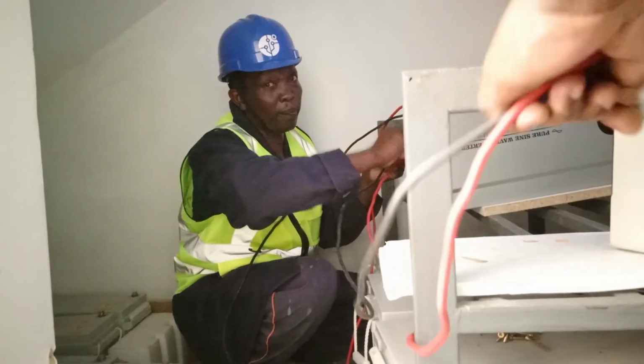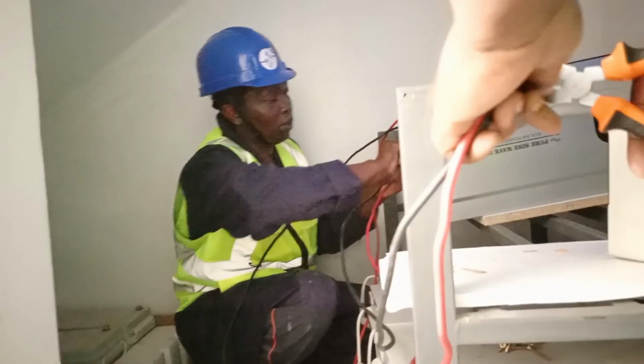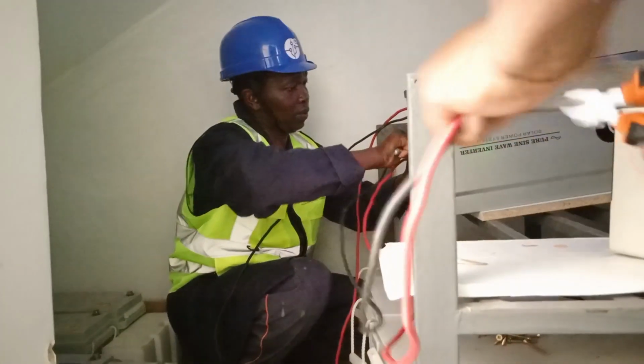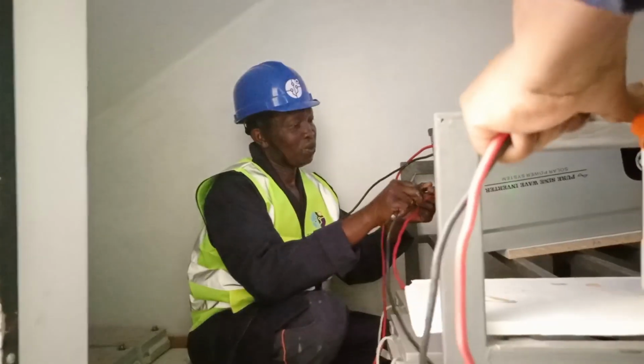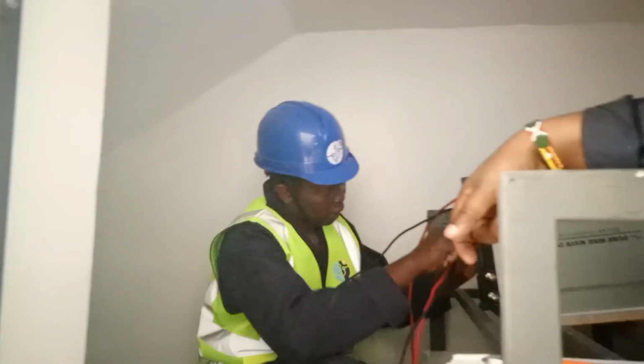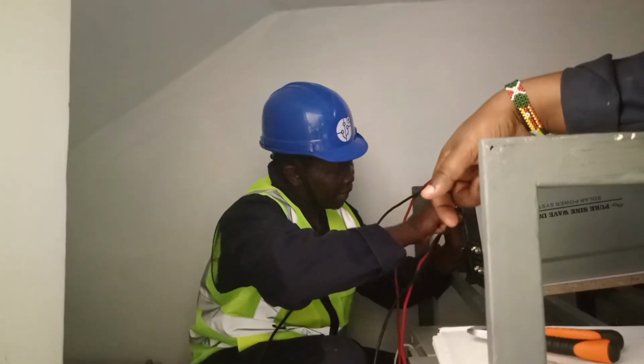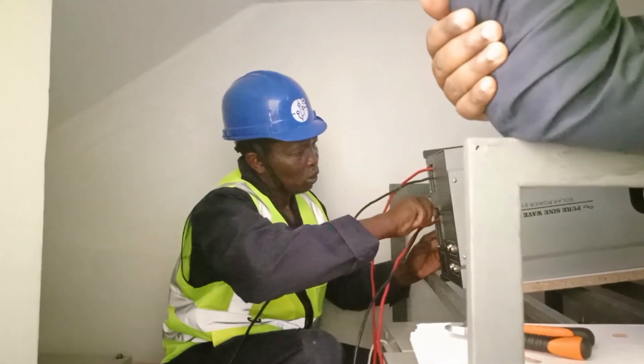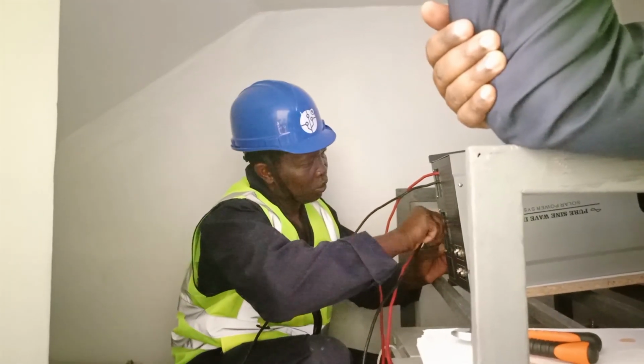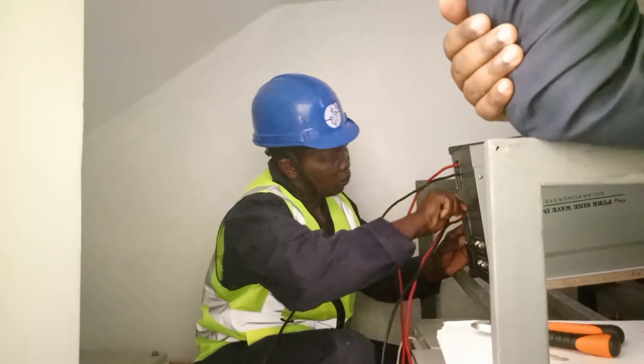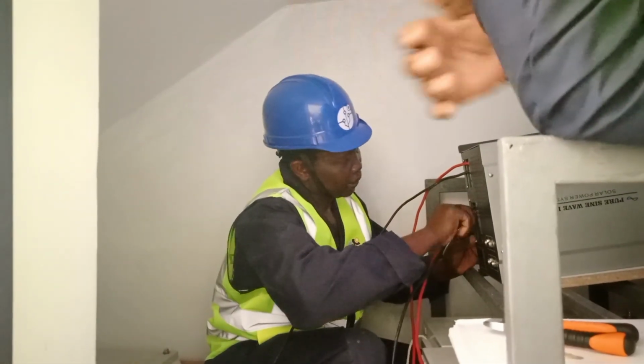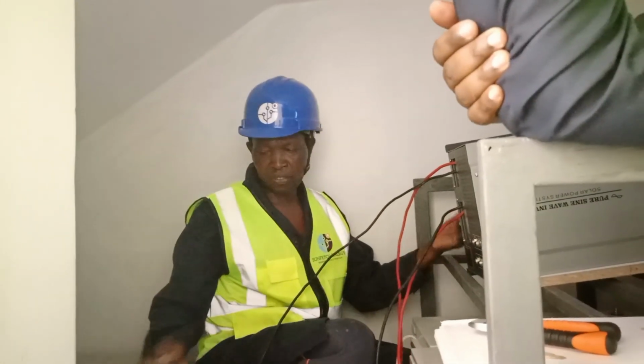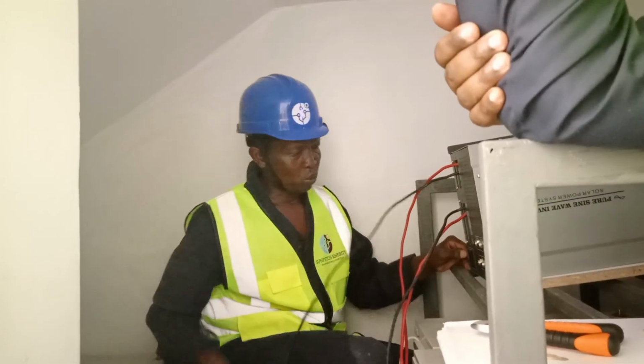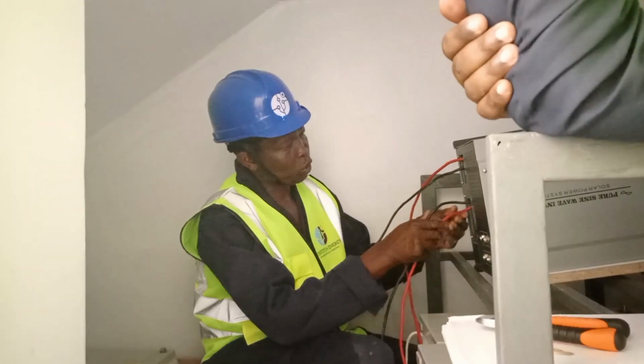And why are you going to do the earthing? I can see the whole house has no earthing, but it's still working. Why should you do the earthing? Let my people understand. It's for power leakage, and mostly when it comes to power discharge, surge problems - it's compulsory, it is very necessary. You can't do without earthing, because that is the discharge of the system. In case of any power leak or surge, that's the discharge path. And it's for safety also, because when you are standing on the floor you may end up being electrocuted.